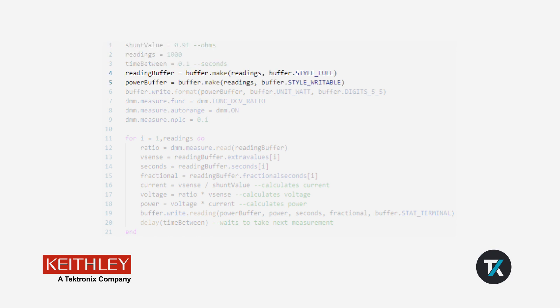Then, we'll make our buffers using the buffer.make command. One is a full buffer and the other is a writable buffer. Since we want to write power readings to the writable buffer, we'll format this one to display watts as the unit.